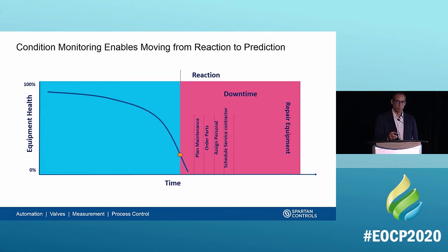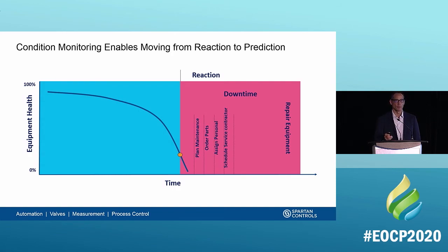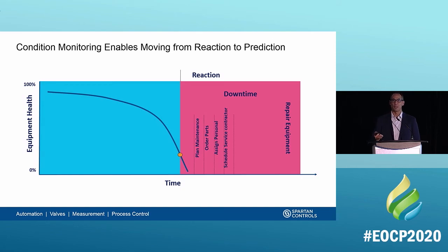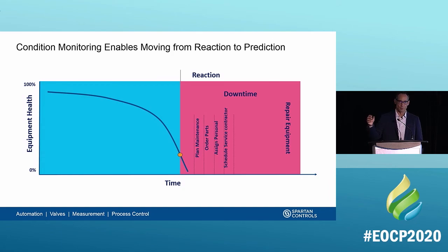From the point of failure we have to schedule people, get parts, remove the equipment, affect the repair, and put it back into service. Another important point about this curve is not just the failure itself, but the performance correlation: as that fault gets worse, the performance of that machinery degrades. A good example is a heat exchanger — as it fouls, we must expend more and more energy to maintain the output temperature. So as the fault condition increases, performance degrades as well.